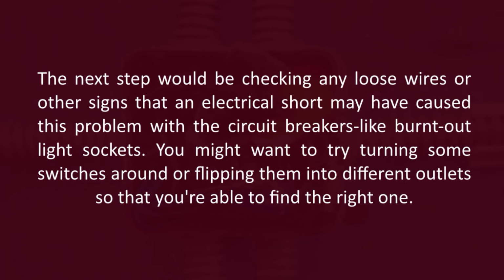The next step would be checking for any loose wires or other signs that an electrical short may have caused this problem with the circuit breakers, like burnt-out light sockets. You might want to try turning some switches around or flipping them into different outlets so that you're able to find the right one. Dead outlets.